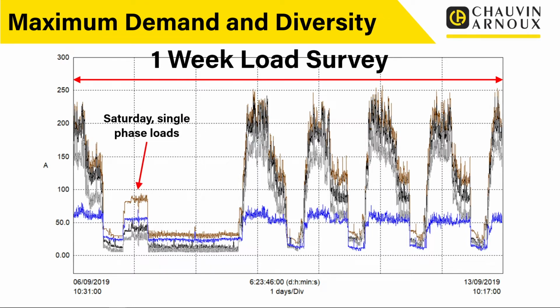I'm guessing this is probably a Saturday. We've got a few loads on there just in the morning, maybe some single phase loads. So that could be just some office workers or bits of lighting, something like that, on a Saturday. Sunday, absolutely dead. No activity going on there. Although there is a base load. If you look at the base loading there, on L1 you're probably looking around the 30-40 amps mark, even as an out of hours figure on a Sunday.